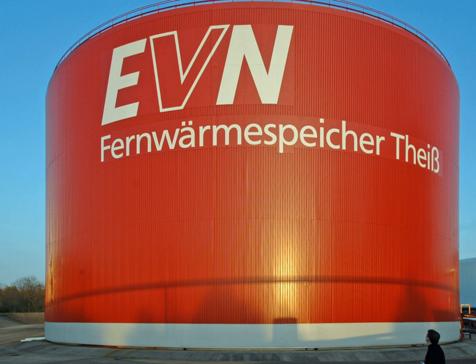Interseasonal storage in caverns has been investigated and appears to be economical, playing a significant role in heating in Finland. Helen Oy estimates an 11.6 gigawatt-hours capacity and 120 megawatts thermal output for its 260,000 cubic metres water cistern under Mustikamäki, fully charged or discharged in four days at capacity, operating from 2021. Meanwhile, 300,000 cubic metres rock caverns 50 metres under sea level in Kruunuvuorenranta near Laajasalo were designated in 2018 to store heat in summer from warm sea water and release it in winter for district heating.